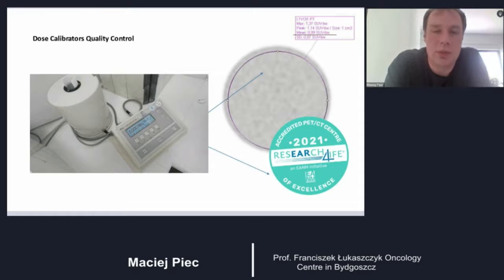So this accreditation, the fact that we are an accredited PET-CT center, means that we need to perform tests quite often, minimum every 3 months. There is a special concentration test. This is a good moment to double check whether the bias or deviation on our calibrator has changed or not. After preparing for the test, we need to input the parameters of the phantom, and when we get the reading, we can find out whether SUV is close to 1.